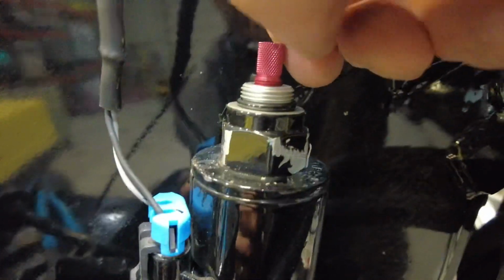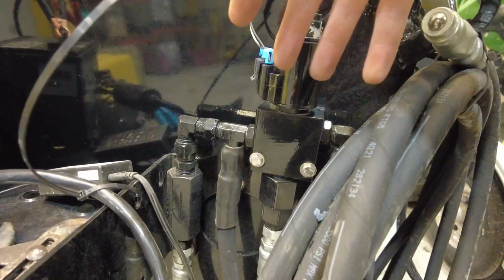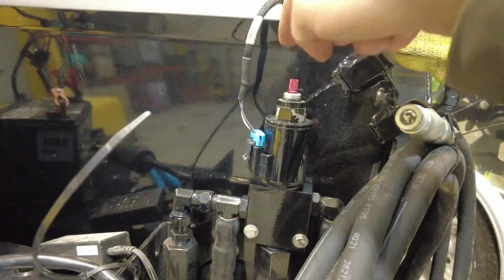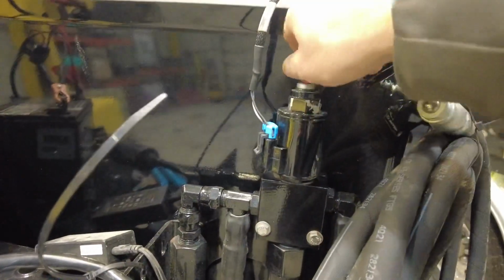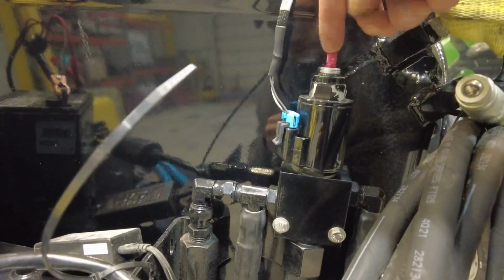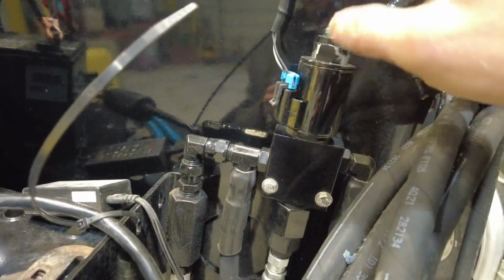So what we're testing here is if you have correct hydraulics going to here and you thread this in, that motor has to spin. If it does not, then we have a hydraulic issue. So this is where you would start. You would troubleshoot, is my issue hydraulic hookup or is it electronics?